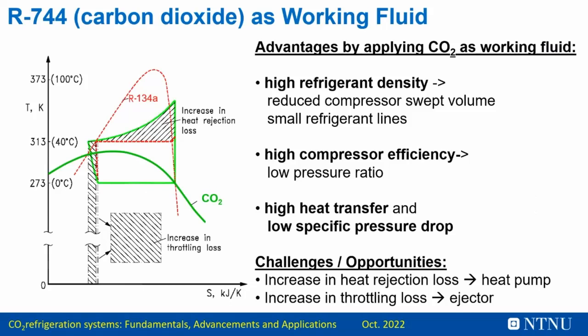So if we then look at CO2 as a working fluid, there are advantages and there are challenges. Let's have a look at the advantages. When we look at the high refrigerant density, this means we have a reduced compressor swept volume and small refrigerant lines, which is super good if you want to do installations. Small lines means less material, more space for insulation and so on. We can also notice that we have a relatively high compressor efficiency compared to standard fluids because we have a lower pressure ratio. And in addition, we have high heat transfer and low specific pressure drop, so we can really tune our heat exchangers to the utmost.